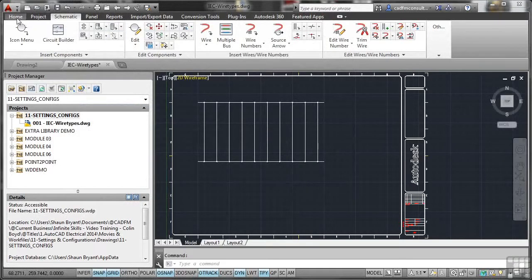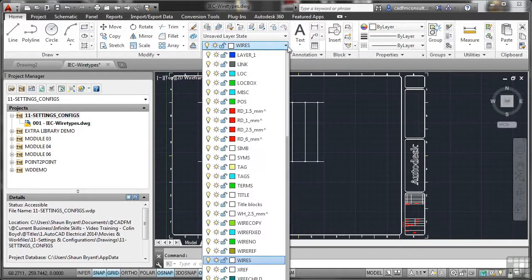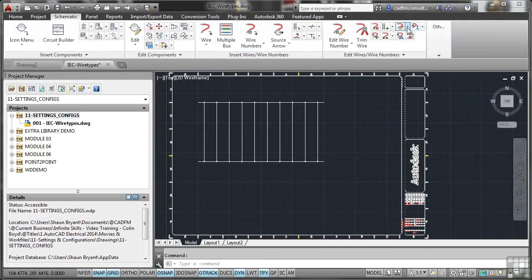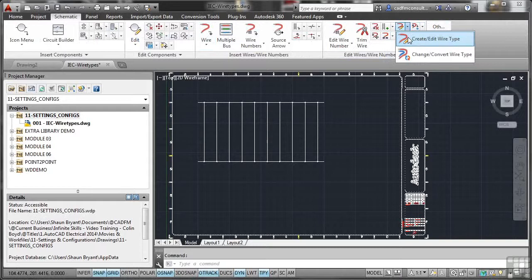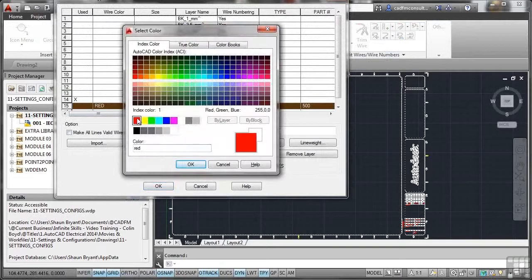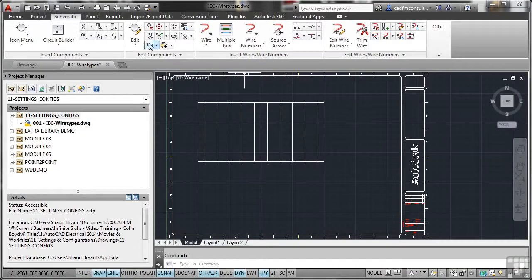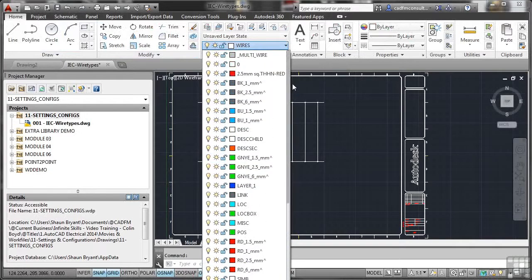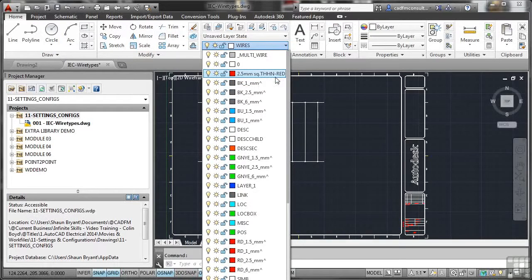Go back to the home tab on the ribbon, go to your layer pulldown and look for your new layer — there it is. But we didn't change the colour, so we need to do that. Don't change the colour here in the layer manager. Instead, go back to schematic, back to edit wires and wire numbers, and click create/edit wire type. Select number 15 and change the colour to red. OK that twice. Now when you go back to the home tab and check for that layer, it'll be near the top: 2.5 millimetres squared, THHN, red — %S then THHN then dash, the colour %C.